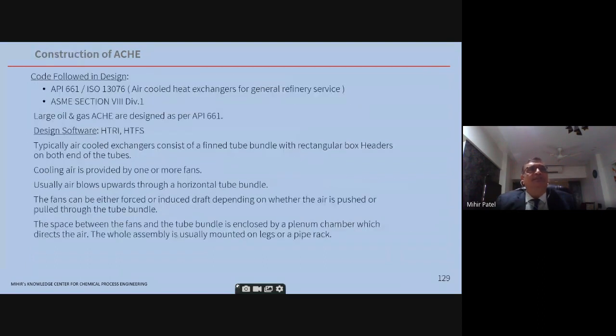Now, one important thing here: the whole assembly is usually mounted on legs or on a pipe rack. This is very important for an air-cooled heat exchanger. Normally, the plant is basically a box unit. In the center is kept the pipe rack, on which the air-cooled heat exchangers are mounted, let's say at 6 meter elevation. This ensures that the air pickup doesn't have dirt and dust from the ground. Plus, the outlet hot air is vented to a sufficiently high location so that it doesn't strike some operator somewhere. It minimizes the area also. So air-cooled heat exchangers located on a pipe rack are very good, and they save on plot area also.